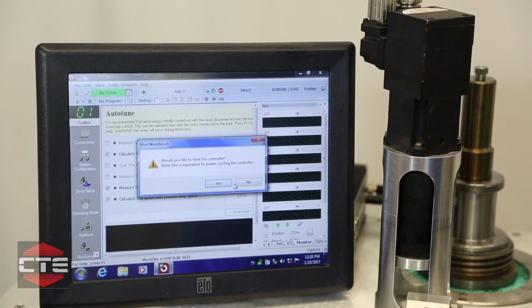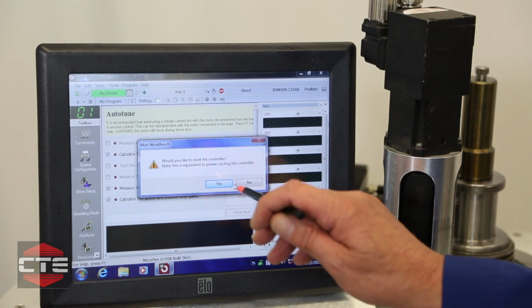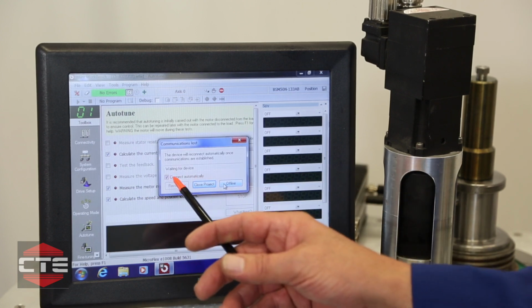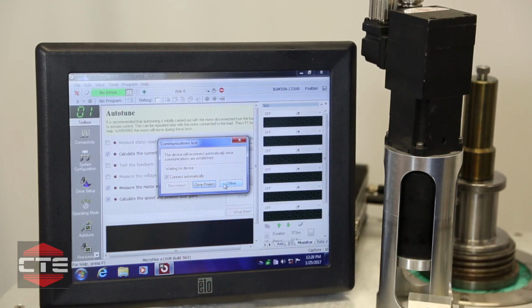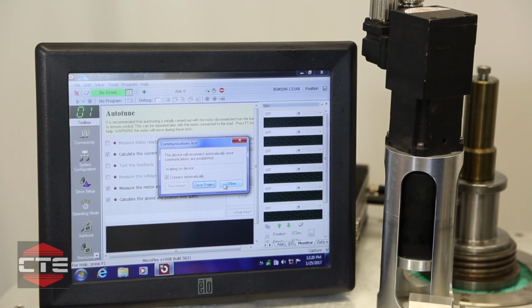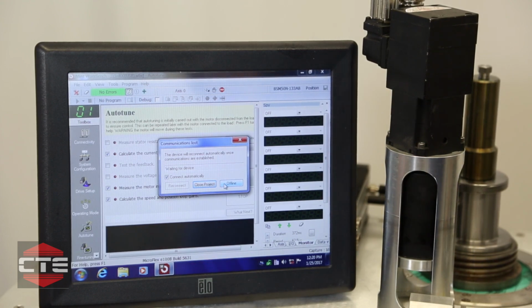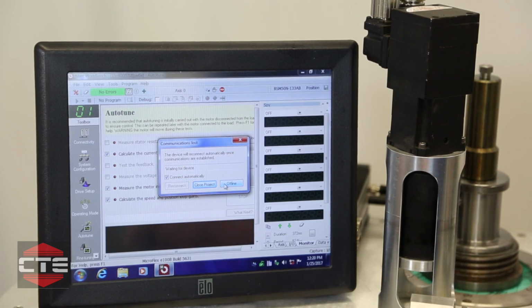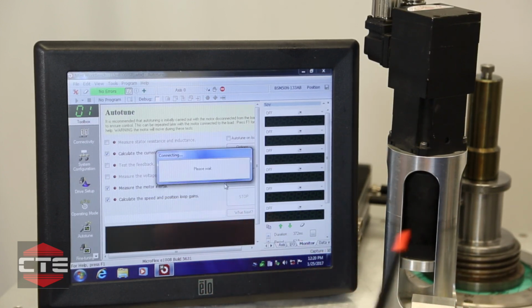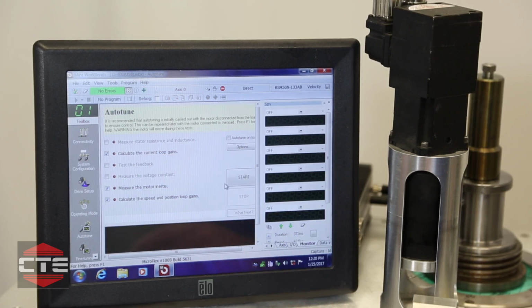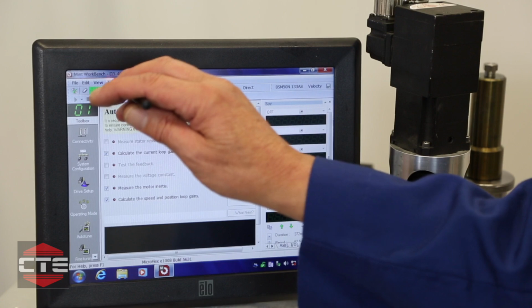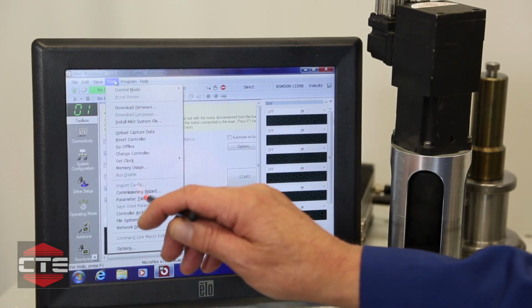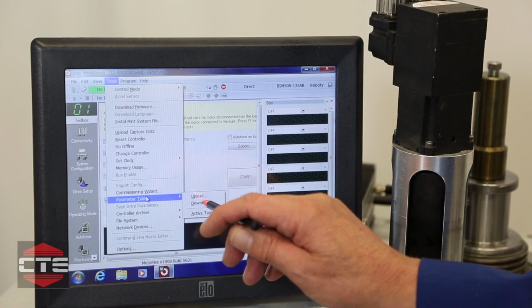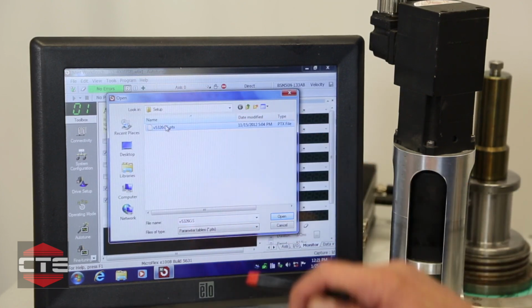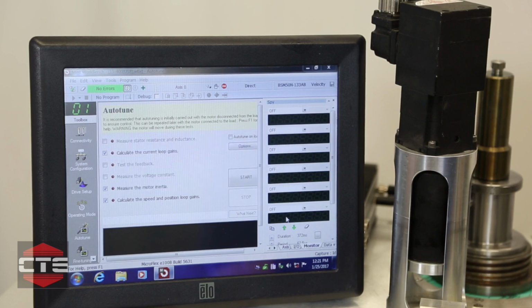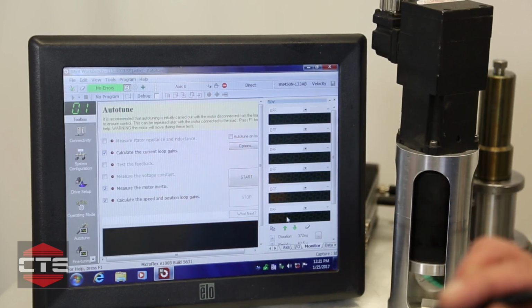Okay, after the firmware is downloaded, it will ask you if you want to reset the controller. And yes, we do. Make sure your Connect Automatically box is checked as on this screen. And that way it will prompt, you don't have to worry about connecting the motor yourself. The software will take care of it. It will detect the device after it can communicate. That completes that part. Back to the toolbar, parameter table, and download. And don't blink or you'll miss this. Open, done. That brings us to the auto-tune function of the motor.